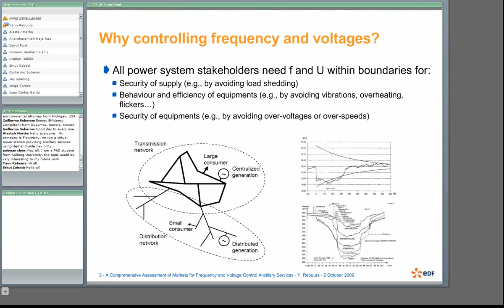Here is an example of the frequency of the UCTE system, continental Europe. As you can see, it exhibits strong variations over time. Here is time and here is the frequency. The target frequency of the UCTE is 50 hertz, and if you lose 1,300 megawatts, it can drop by 50 millihertz.